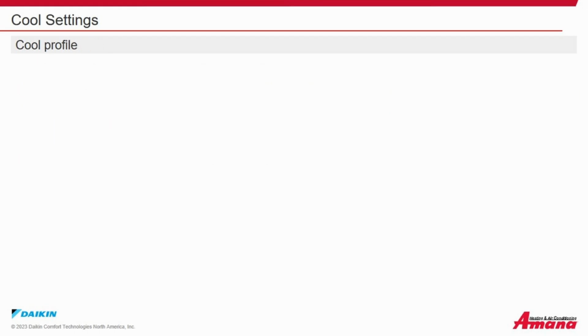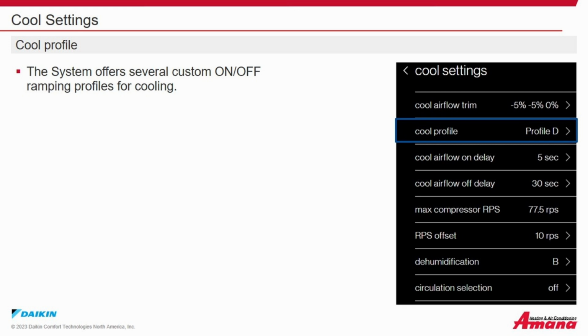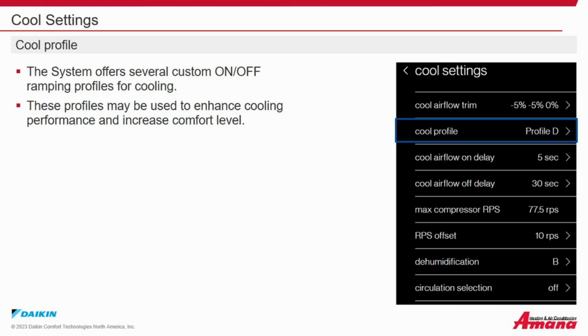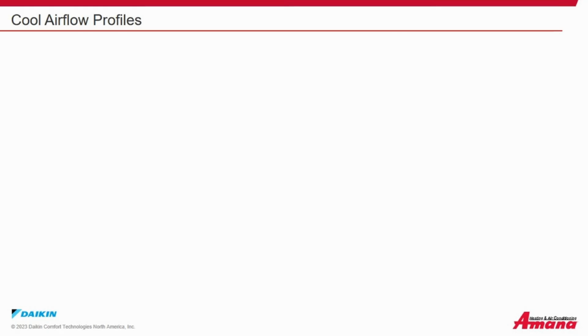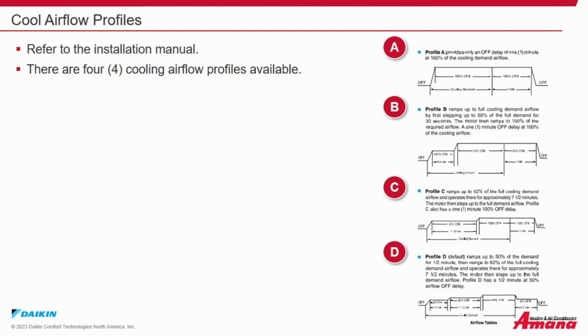Cool profile. The system offers several custom on and off ramping profiles for cooling. These profiles may be used to enhance cooling performance and increase comfort levels. Cool airflow profiles. Refer to the Installation Manual. There are 4 cooling airflow profiles available. All residential inverter systems are factory set to Profile D.